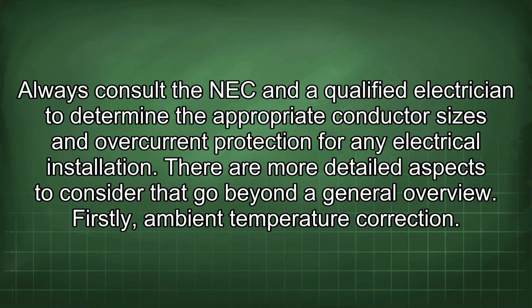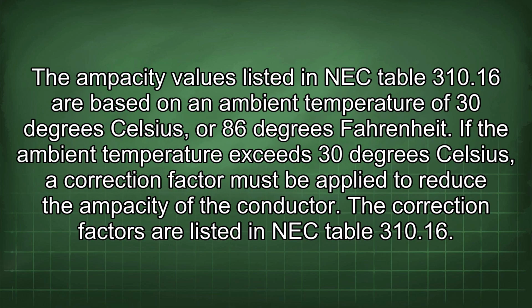Firstly, ambient temperature correction. The ampacity values listed in NEC Table 310.16 are based on an ambient temperature of 30 degrees Celsius or 86 degrees Fahrenheit. If the ambient temperature exceeds 30 degrees Celsius, a correction factor must be applied to reduce the ampacity of the conductor. The correction factors are listed in NEC Table 310.16.